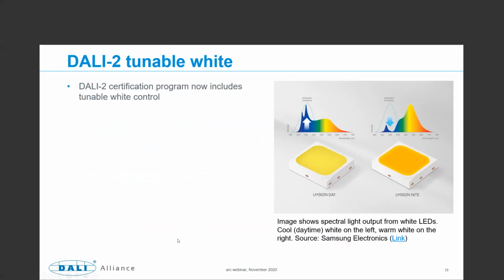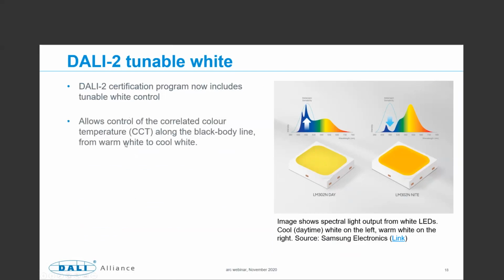So tunable white is already included in the DALI-2 certification program that started in January this year. And you'll see a number of DALI-2 tunable white drivers already in our product database. This allows control of the correlated color temperature, the CCT, along the black body line from warm white to cool white. And these drivers implement this part of the standard. It's called part 209, and it's also known as DT8. So you'll sometimes hear this on the market, device type 8 or DT8. But for tunable white, it's the TC color type. So tunable white is a good way to explain what you're getting here.